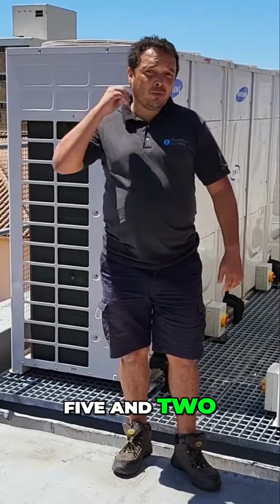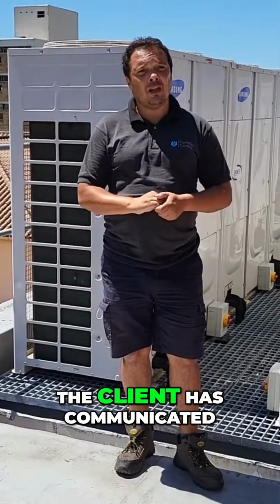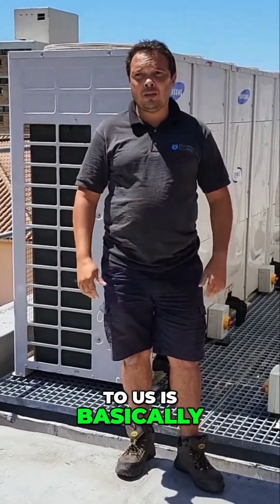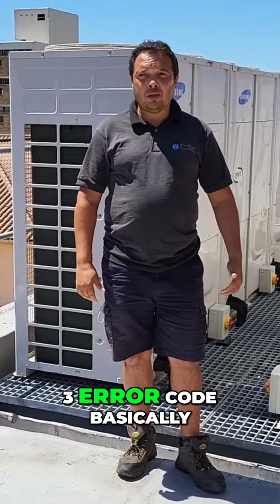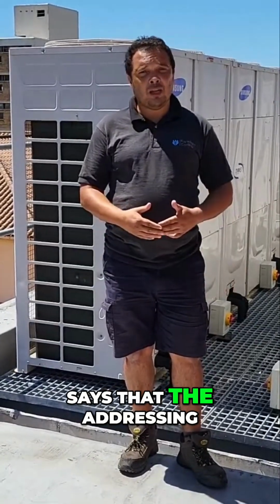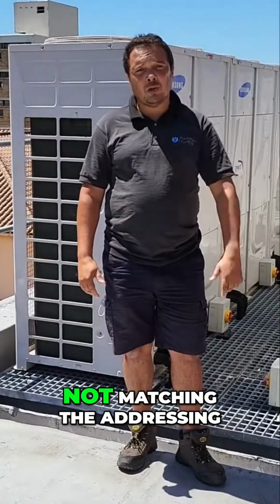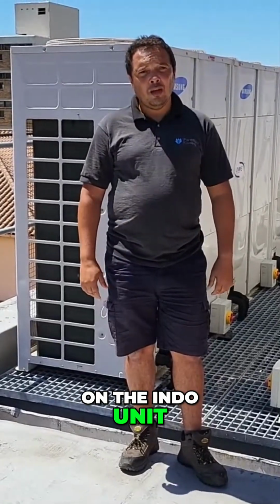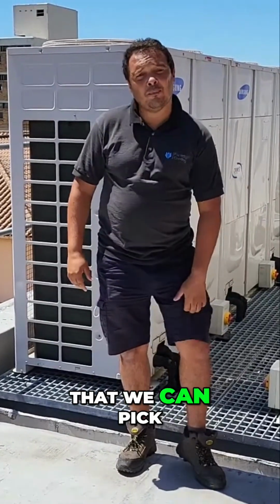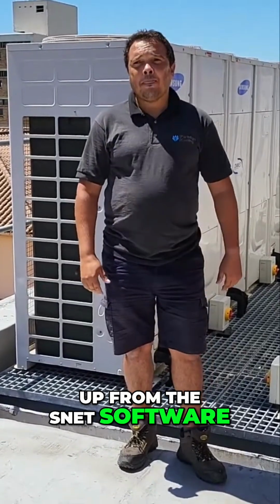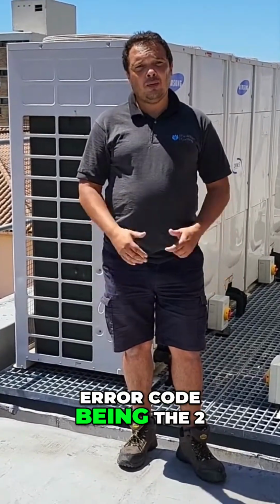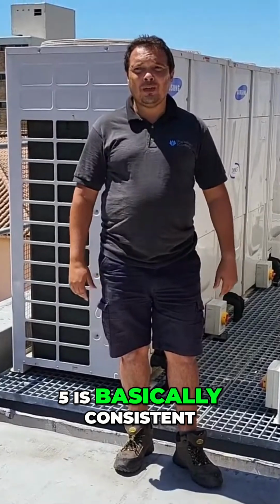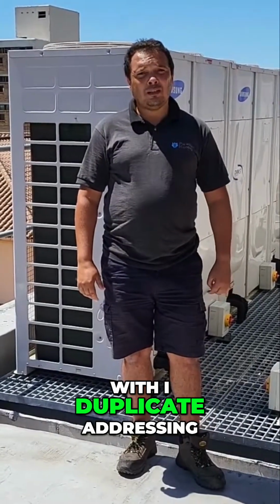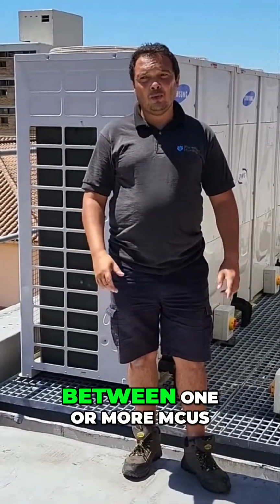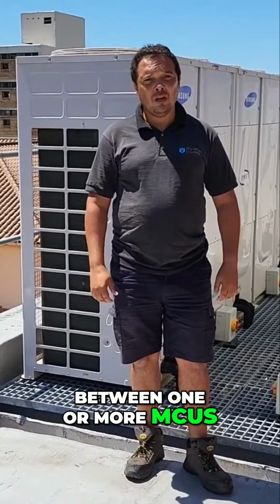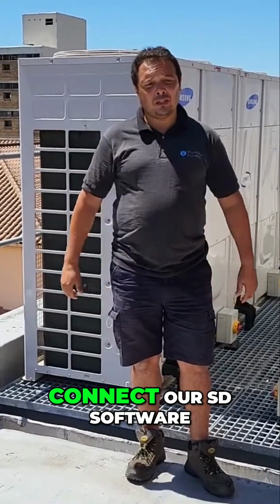The 213 and 215 error codes the client communicated to us are consistent with known issues. The 213 error code basically means the addressing on the MCUs is not matching the addressing on the indoor unit, which is something we can pick up easily from the SNET software. The 215 error code is consistent with duplicate addressing between one or more MCUs.